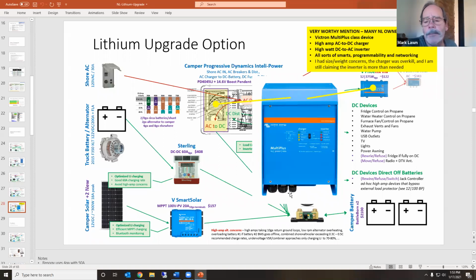Hey Joe, quick suggestion. Next time you plug in and it trips the GFCI on the shore power receptacle, after you reset it, try connecting a ground wire from where all the grounds attach on the camper down to something metal that the GFCI receptacle is also grounded to, just to see if there's continuity in the ground and if that fixes the problem. It might. Basically run a jumper wire from the clamp on the outside of the camper to the box, because the GFCI is probably thinking your camper is a device without a ground path. Yeah, I can do that, even at home, since I have a GFCI in my garage I plug into sometimes. That would be a good test. Thank you.